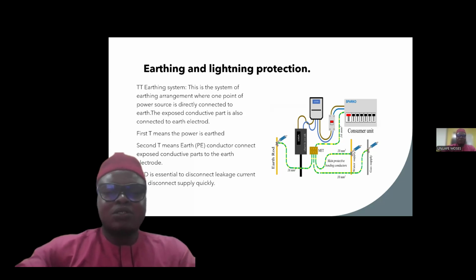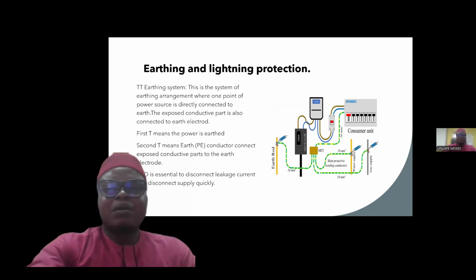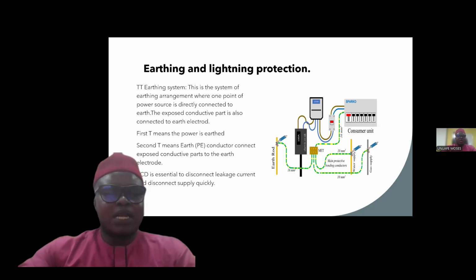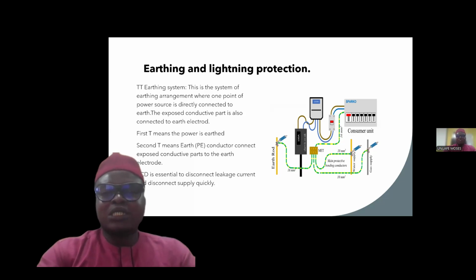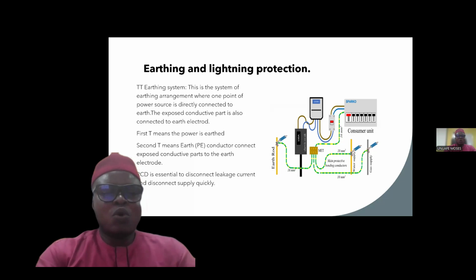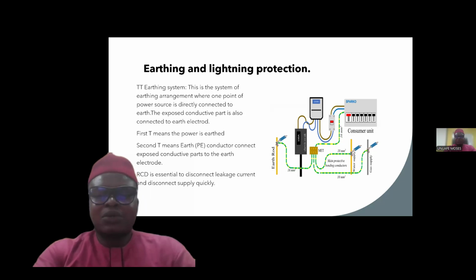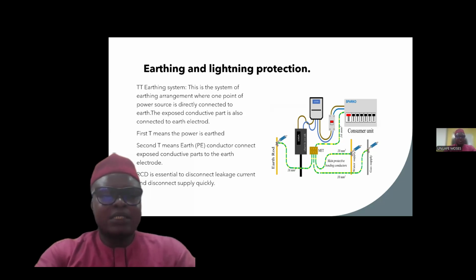This is done just to ensure that protection is paramount on that very particular area. There is no reliable metallic return path from the utility, so independent local earthing gives a safe flexibility. That is just what we can achieve. And anybody that is using this TT system of earthing should ensure that the input supply to the distribution panel should be provided with an RCD, which is a residual current device.